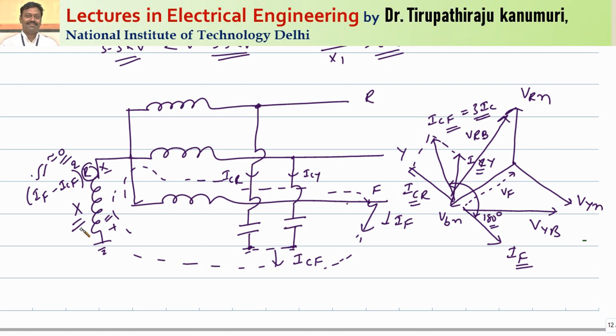There is a disadvantage: when lightning surges fall on the system, the wave should pass through the respective phase to ground. However, because of the inductor's property seen in switching transients, when the wave arrives, the inductor initially acts as an open circuit, causing the entire wave to reflect back. When reflected, the voltage becomes double, and due to this cumulative phenomenon, switching transients or surges will be very high with reactance grounding. The system must be able to withstand that — that is a major limitation.